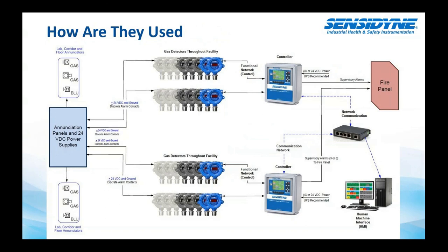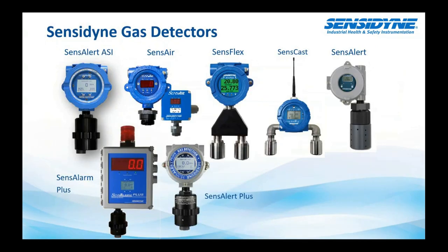A typical system you'll see, this obviously is quite a few points, but you'll have your gas detectors throughout the facility. As a rule, most of our customers keep their safety systems separate from their control systems. So we do offer controllers that can accomplish that for you, which will feed back into your fire panels or even your control systems. But as a rule, these are somewhat separate with just communications back into other systems. And then those can communicate to your annunciation panels for your alarms and strobes and horns and different things like that. It's kind of the family of products.